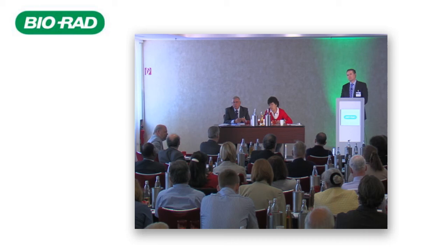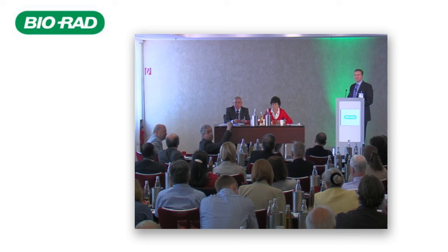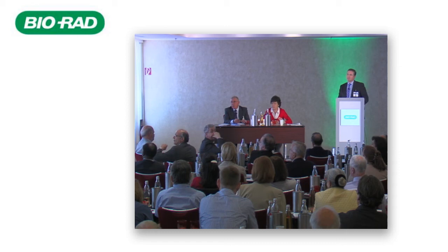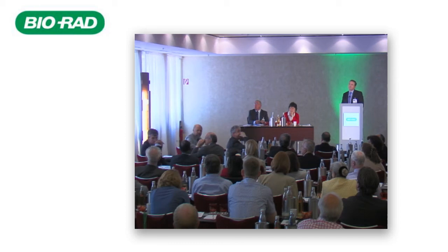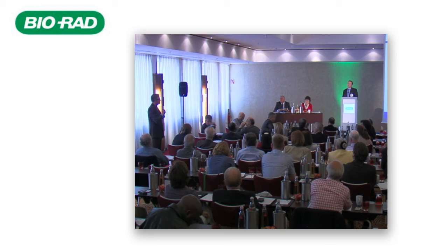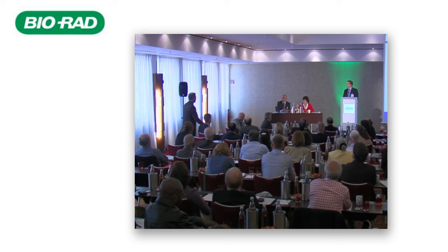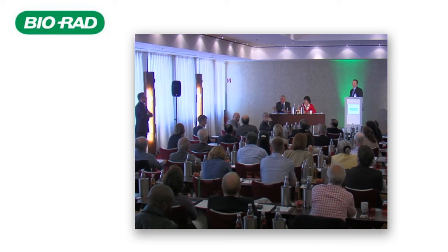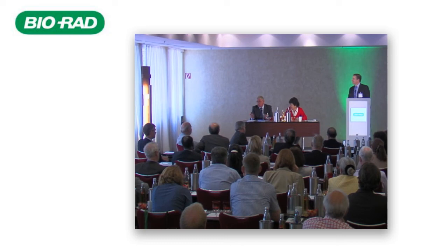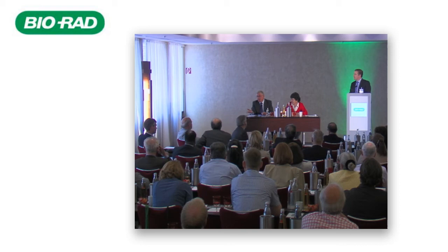Troponin, another example. Actually, troponin's a great example. A few years back, a best practice guideline came out that said troponin should have a CV of 10% or less. And the manufacturers started scrambling to see who could be the first out with an assay to meet that guideline. Where did the 10% come from? I know where it came from. It came from a group of experts, but it's based upon empiricism. It's not scientific, it's not objective.